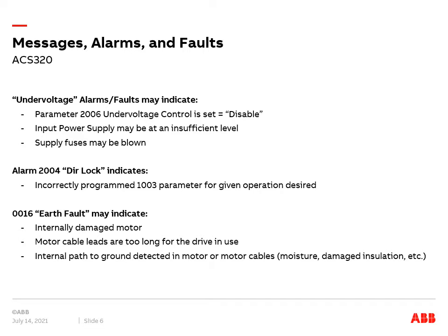Fault 16, Earth Fault, can be caused by a damaged motor, motor cables that are too long, or an internal path to ground detected in the motor or motor cables. This can be caused by moisture in the motor or damaged insulation. Moisture in the motor oftentimes causes numerous intermittent nuisance trips on earth faults.